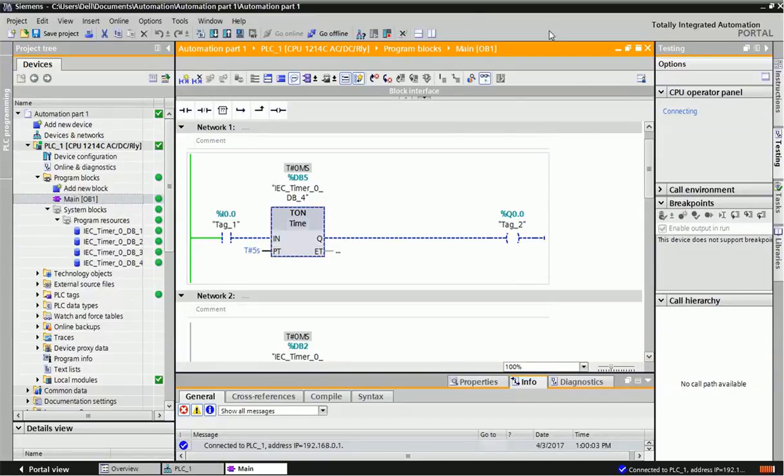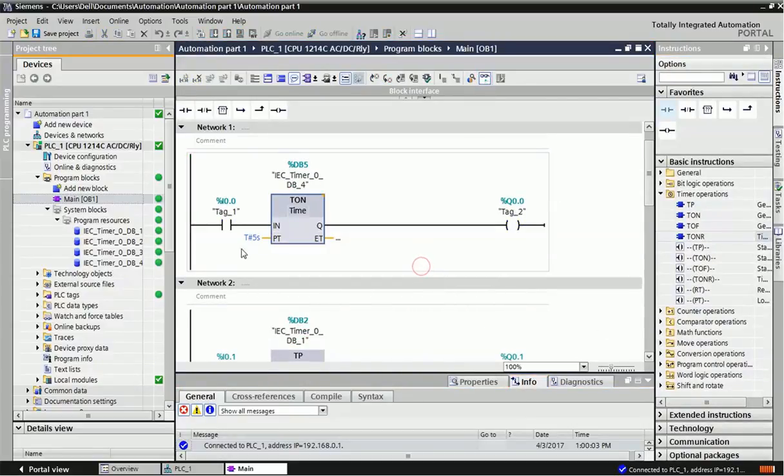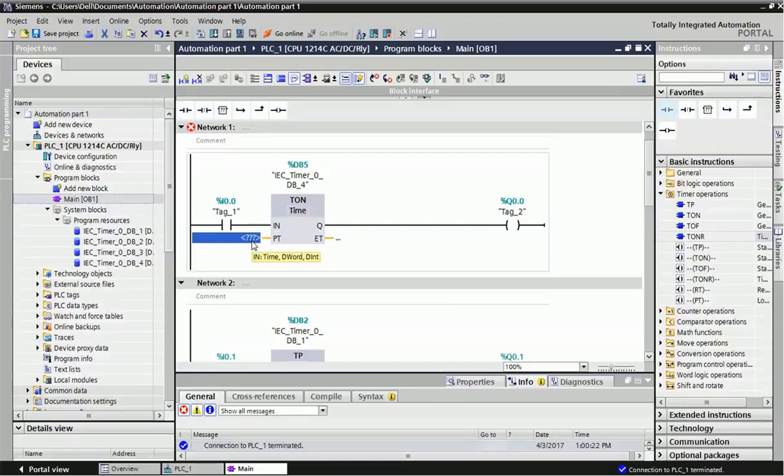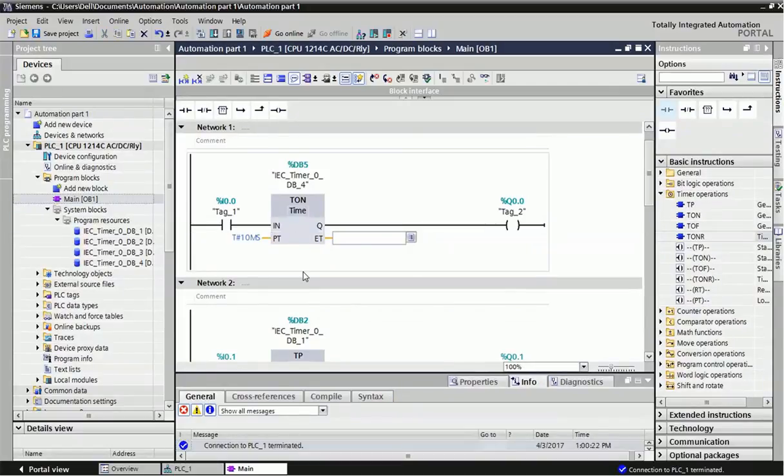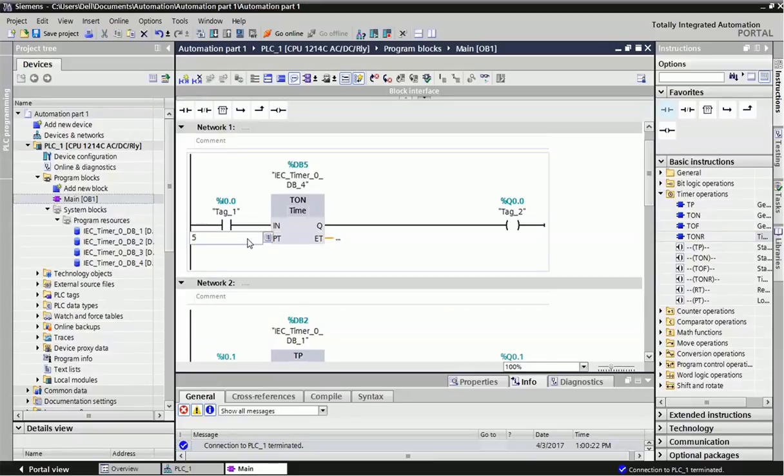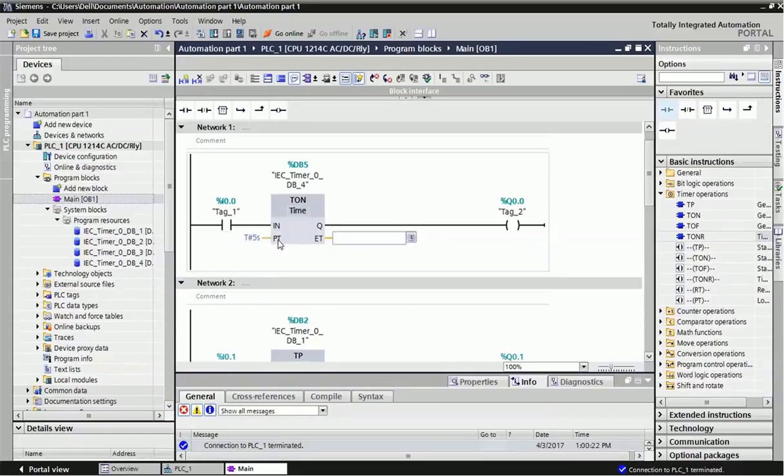If you have questions about how to enter time values: this timer generally takes values in milliseconds. If I give T#10ms and enter, it takes milliseconds. If you want to give seconds, just write the value and then 's', then enter, and it will take the time in seconds.